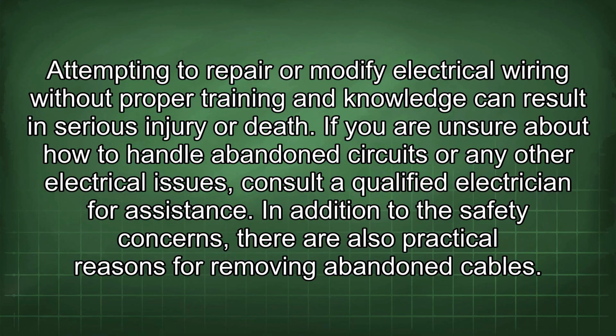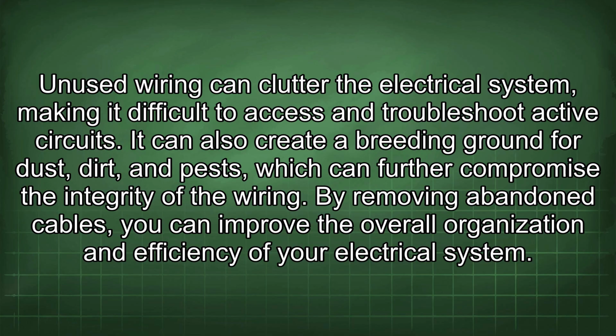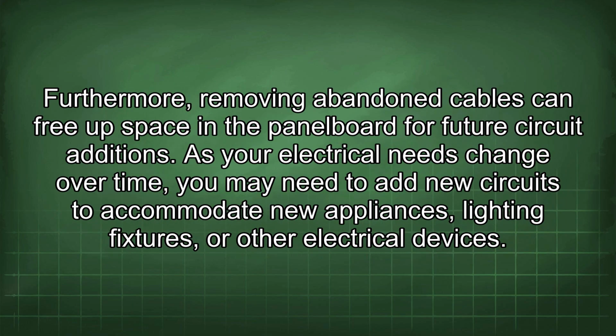In addition to the safety concerns, there are also practical reasons for removing abandoned cables. Unused wiring can clutter the electrical system, making it difficult to access and troubleshoot active circuits. It can also create a breeding ground for dust, dirt, and pests, which can further compromise the integrity of the wiring. By removing abandoned cables, you can improve the overall organization and efficiency of your electrical system. Furthermore, removing abandoned cables can free up space in the panel board for future circuit additions.